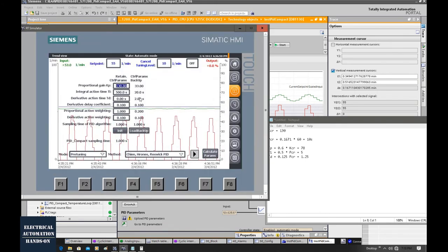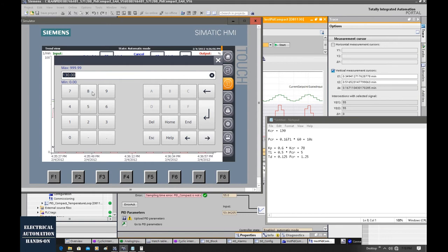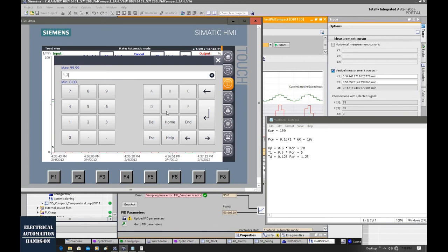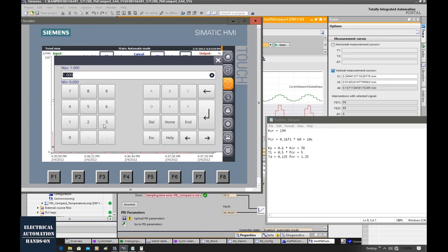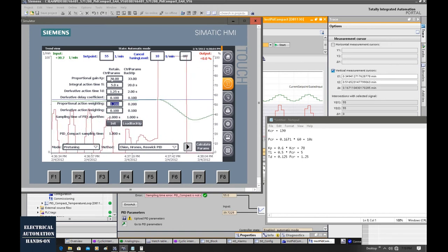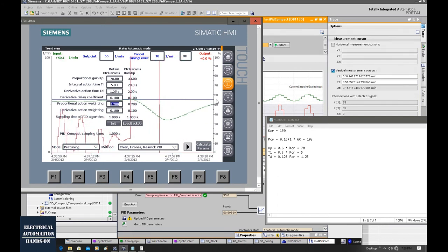Those values will be used as our PID parameters. The Kp we will type in is 78. This Ti is 5 seconds. This Td is 1.25. I will return this proportional action weighting back to 0.2. After we change these three PID parameters, we will see this feedback and the control data process approaching our setpoint.